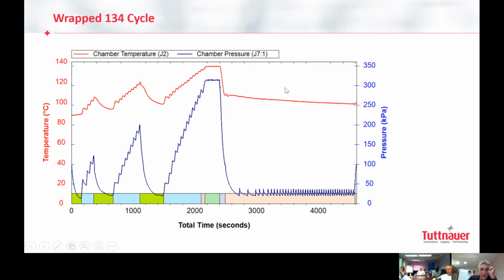So this is what we see here. You see the pulses? Can you see the graph? Yep, we can see it. So you have to understand, this graph is in kPa, kilopascal. 100 kPa is your zero, or 0 psi G, okay? And this is like the 0 psi A or 30-inch mercury. This is 0-inch mercury and 0 psi G. So we start from here, we go down to like 20%, removing 80%. Now the reason you see this one, you will understand later, because of how our steam generator, our vaporizer, functions. So you will see why it looks like this.